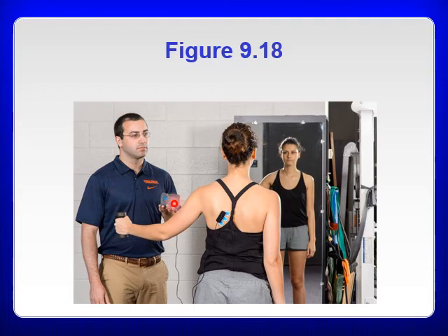He sets the unit to a certain sensitivity. As she gets that muscle to contract, a little beep or a light will flash on this unit telling her that she's getting a good adequate contraction. What this person likely has difficulty doing is elevating their shoulder without hiking. Getting good contraction here will prevent that, because you don't want the shoulder to hike while you're elevating your humerus. And that's what she's basically learning to do. So that's one application of this.